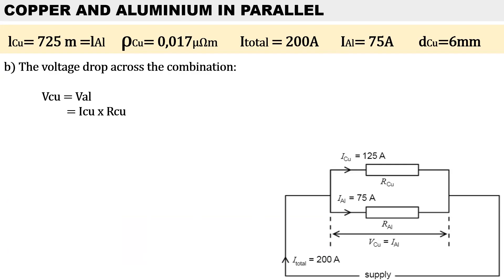To determine the voltage drop across this combination: because it's a parallel combination, voltage remains the same. Therefore, the voltage across the copper and aluminum conductors should be equal. We have all the values for copper, so we use copper as our reference. The current through copper is 125 amps and the resistance of copper is 0.436 ohms. Therefore, the volt drop across the parallel branch is 54.5 volts.